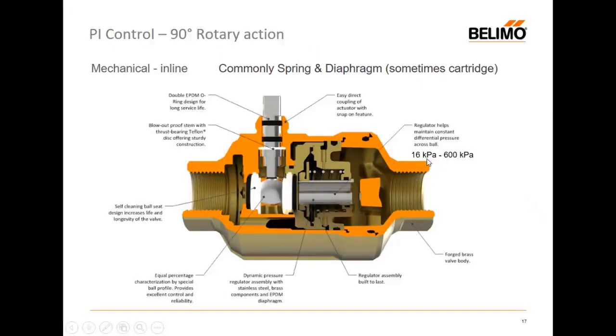That's also interesting if that valve's on the index circuit, because on the index circuit, if I'm only measuring 16 kPa, I do know I've got my flow rate through the circuit, but I'm doing it with a minimal resistance. And any resistance on the index circuit affects directly the pump selection. So having a low pressure drop at the index and knowing what that pressure drop is kind of useful for saving energy. So very interesting for that. But you can see some of the difficulty here in trying to measure the flow. We've got an awful lot of internal complexity. So measuring directly the flow on this kind of valve, probably not possible, certainly not in my experience.